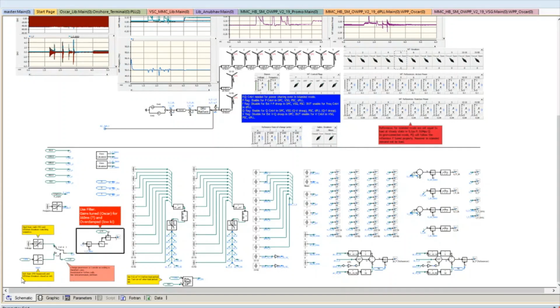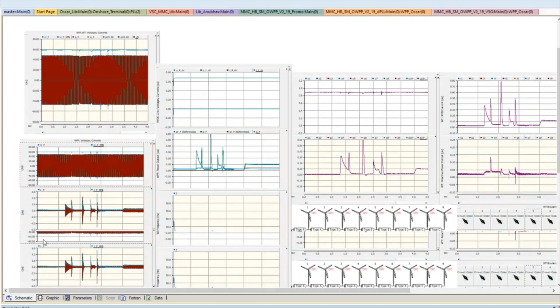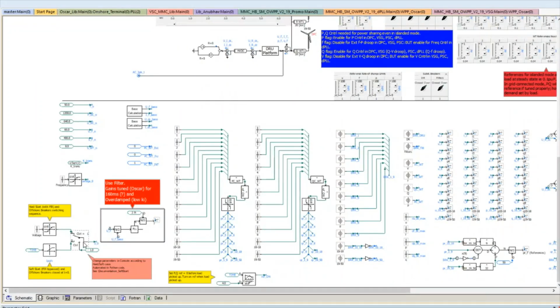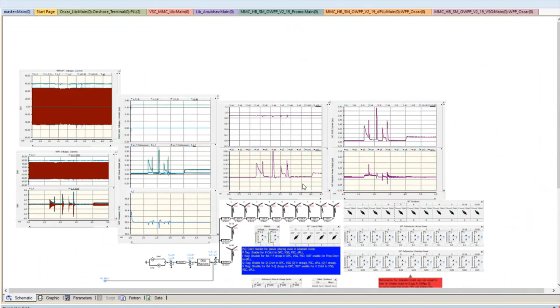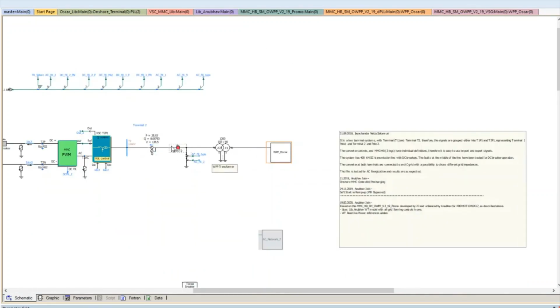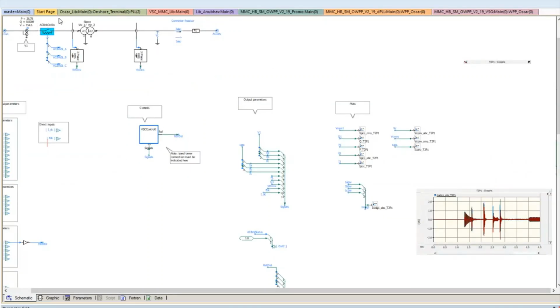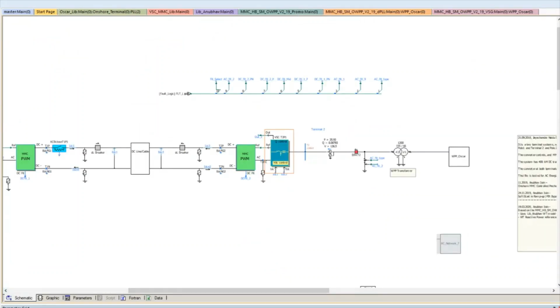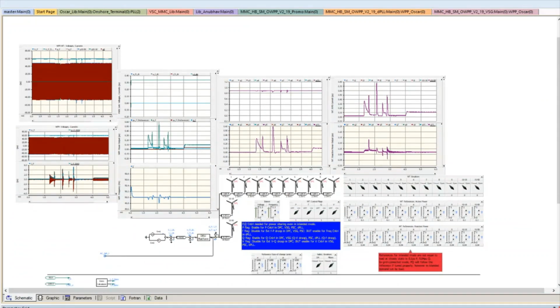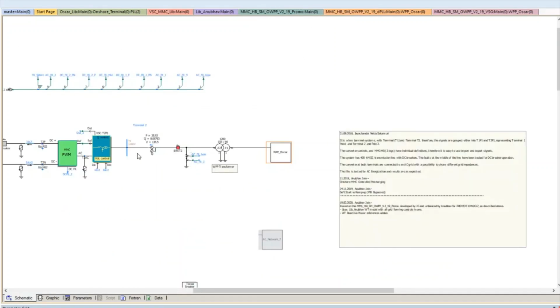And what you see here on the left corner is an option for doing soft start energization or hard energization. In the soft start, basically, as the wind turbines ramp up the voltage slowly, everything is connected. So the pre-insertion resistor to energize the offshore transformer and the converter cells is bypassed, and everything energizes together with the wind turbines. However, if you choose the hard switching, then first the wind turbines are energized in one go, and then they connect to the offshore network with the PIR inserted, and after some time the PIR is bypassed. I'll show you a bit more detail on the energization sequence later, which would help make things clearer.